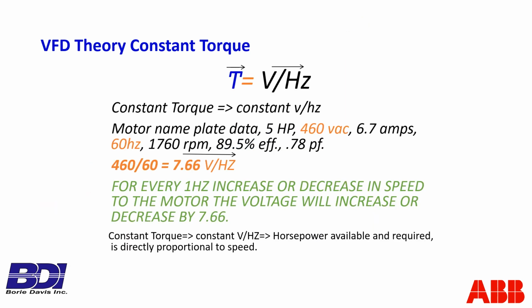The torque equation electrically is boiled down to: you want constant torque, you provide constant volts per hertz. So out of all that nameplate data you entered, telling the drive what size the motor was, it uses that voltage and frequency that you inputted, or you just simply confirmed, because there are default data in the drive. That's set up and simply did division of 460 volts divided by 60 hertz and comes up with a solution of 7.66 volts per hertz. If I maintain 7.66 volts of increase or decrease for every 1 hertz increase or decrease in frequency to the motor, then I'll maintain a constant volts per hertz, which means constant torque is available.